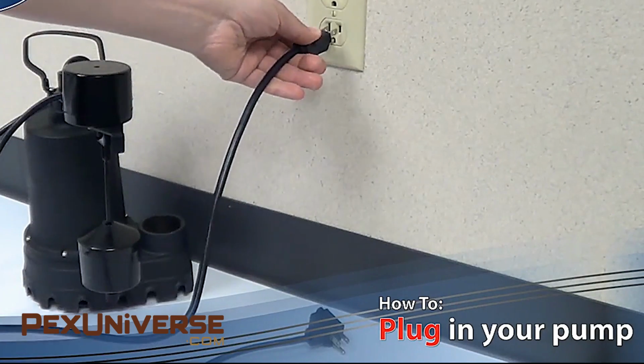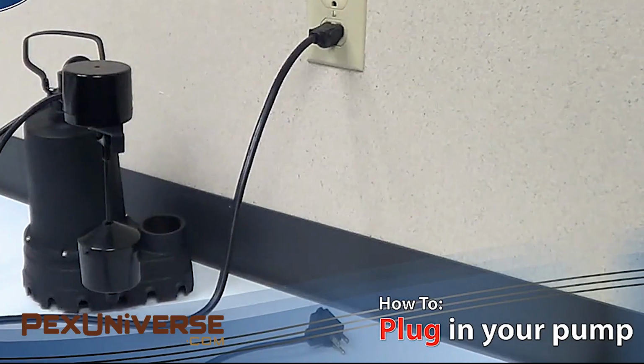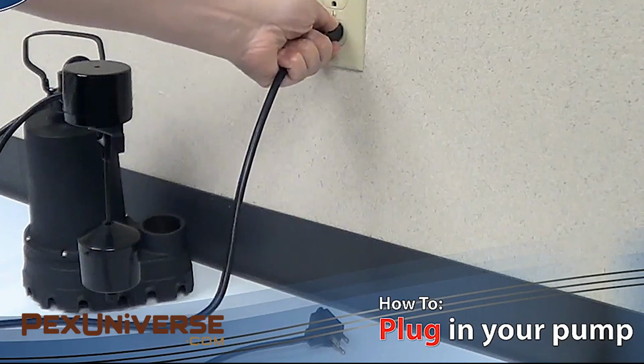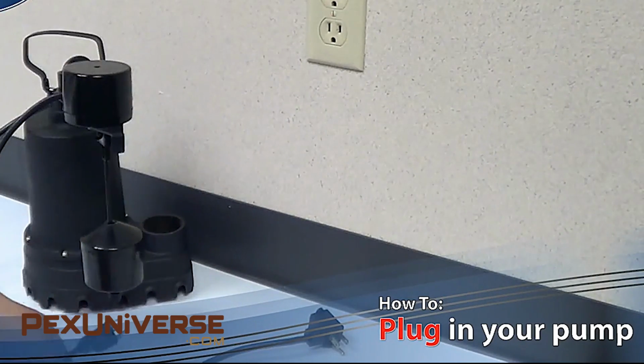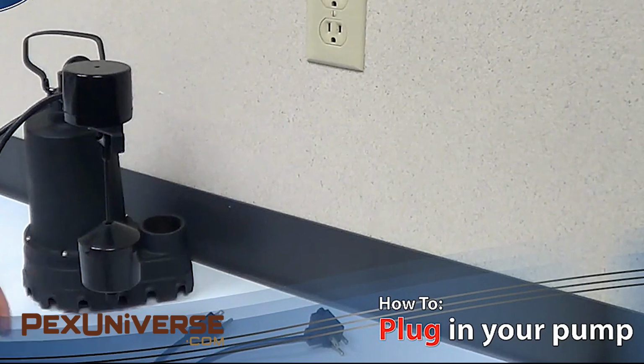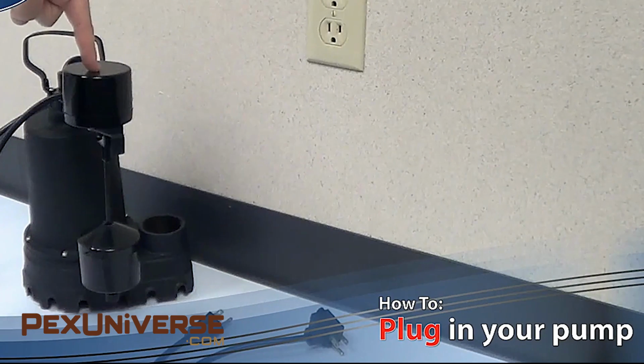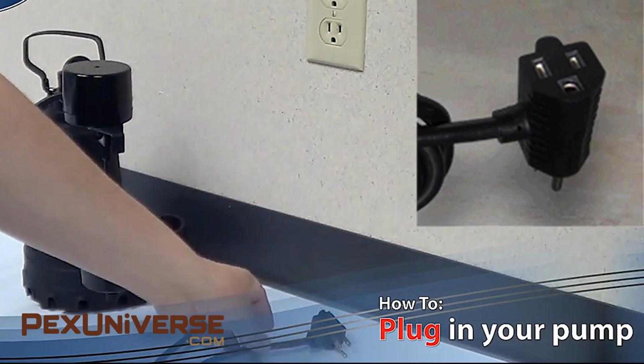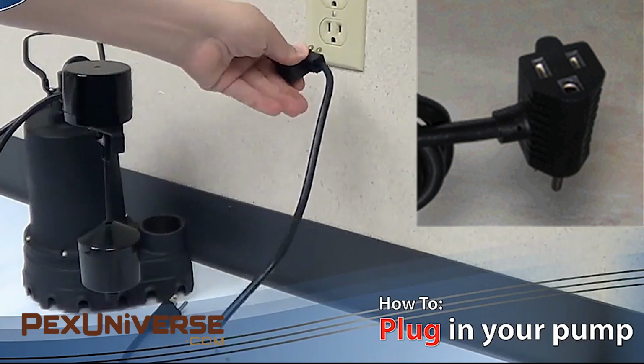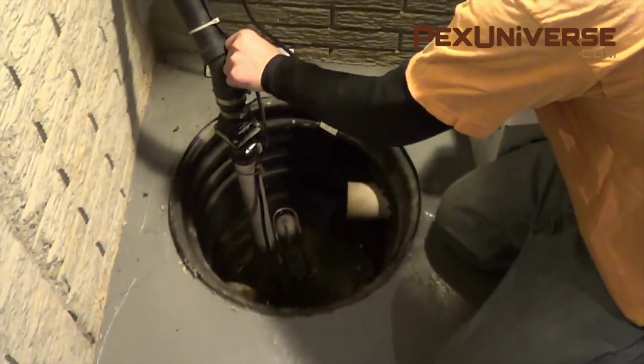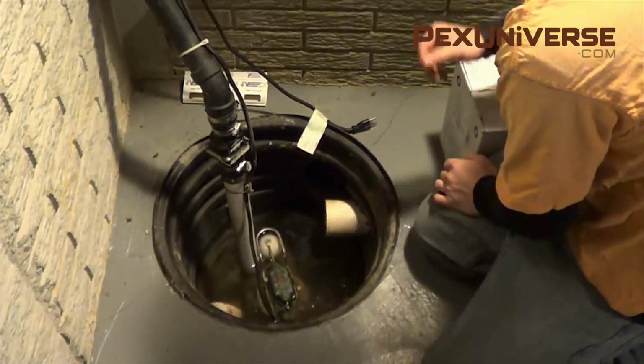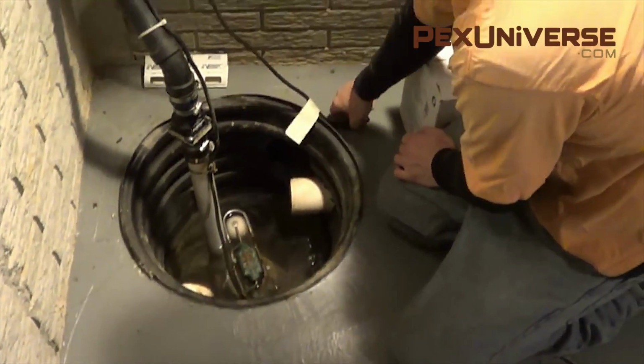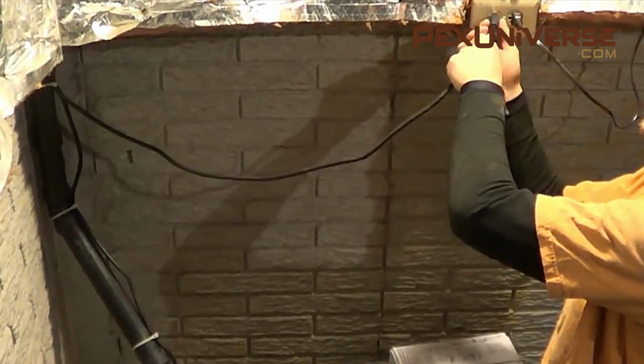These pumps are mostly used for manually dewatering basements, pools, and similar applications. These aren't common for using in sump basins, but you can couple this with a piggyback switch to allow for automatic operation if you wanted to. In short, a manual sump pump must be turned on and off manually. An automatic sump pump has a switch or float wired to the pump that activates the pump when water reaches a certain height, and turns the pump off when the sump pump has drained the water.